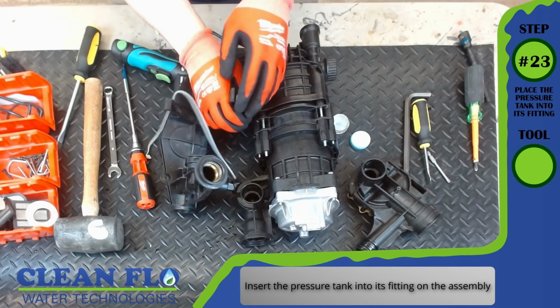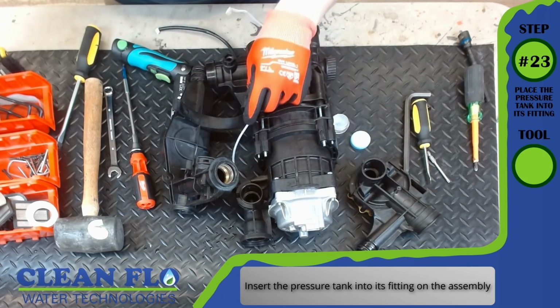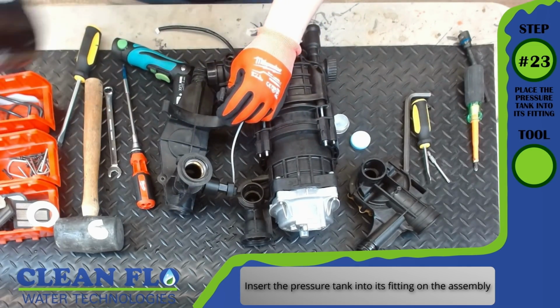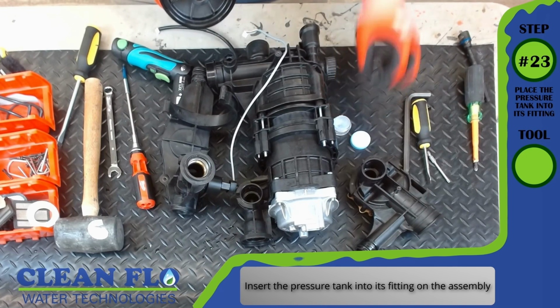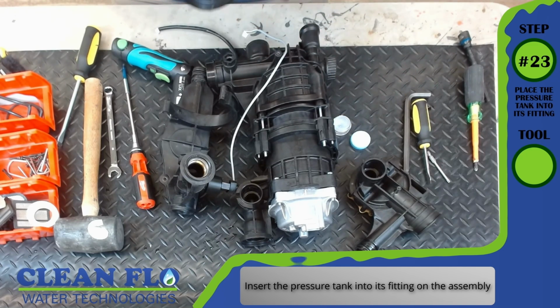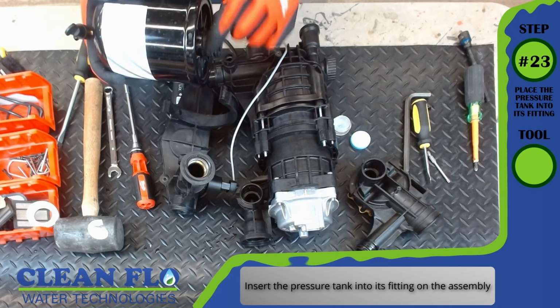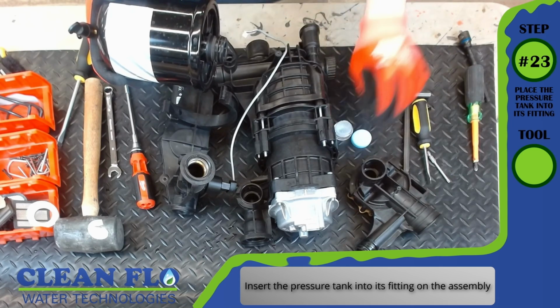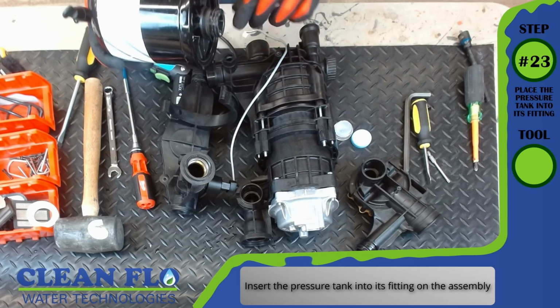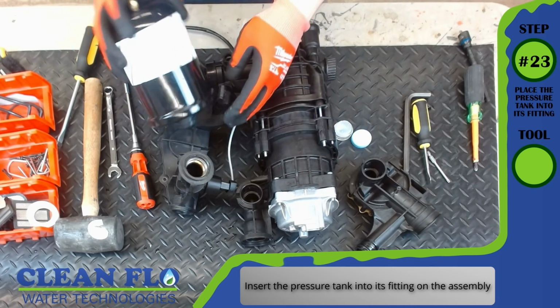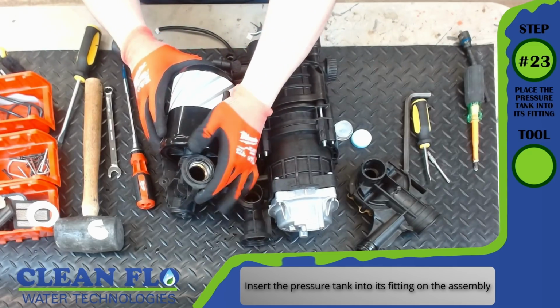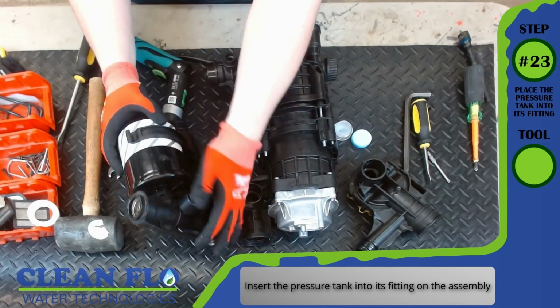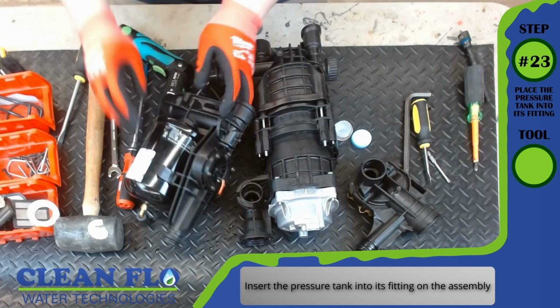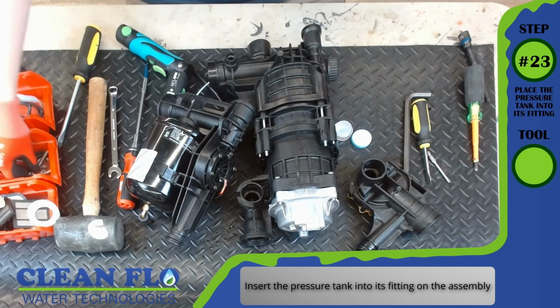Step number 23, place the pressure tank into its fitting. No tool required. Insert the pressure tank into its fitting on the assembly. Again, ensure you're using silicone lubricant to lubricate the O-ring, and this will ensure a proper seal and easy installation. Apply force directly forward, and the pressure canister will slide directly into its fitting.